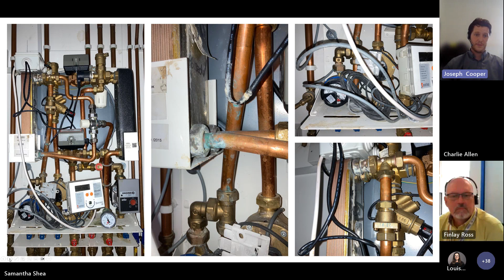So recommendations from the optimisation study then identified 3 immediate adjustments that could be made to increase efficiencies. These are to close bypasses at the top of the HIUs to reduce flow rates and lower the return temperatures. Reduce pump differential pressure set points. So the combined points above would save around £30 per apartment annually, or around about 7,200 per annum, which is a pretty much instantaneous saving, which was great.